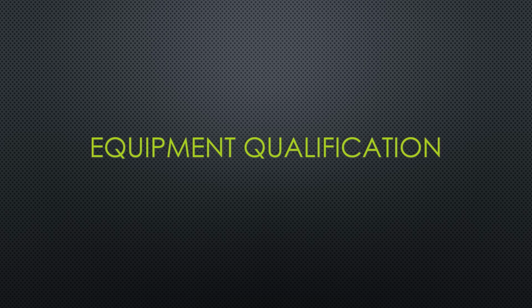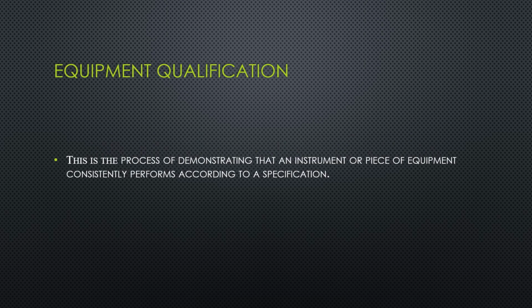Today we'll learn about equipment qualification. Equipment qualification is the process of demonstrating that an instrument or piece of equipment consistently performs according to a specification. So equipment qualification says that each and every part of the equipment or the instrument will produce results according to the specification limits that have been established, as well as within the acceptance criteria.